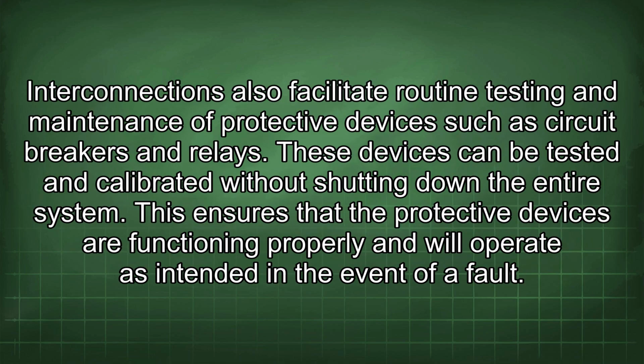Interconnections also facilitate routine testing and maintenance of protective devices such as circuit breakers and relays. These devices can be tested and calibrated without shutting down the entire system. This ensures that the protective devices are functioning properly and will operate as intended in the event of a fault.